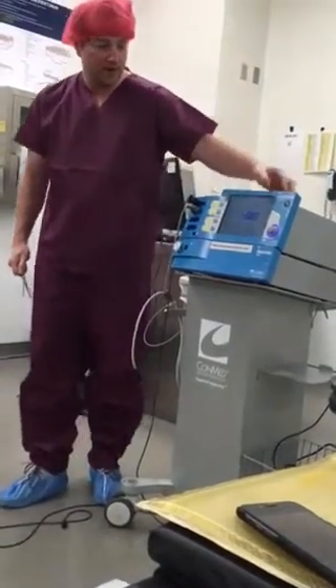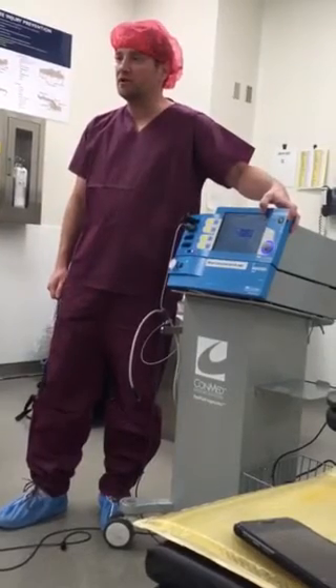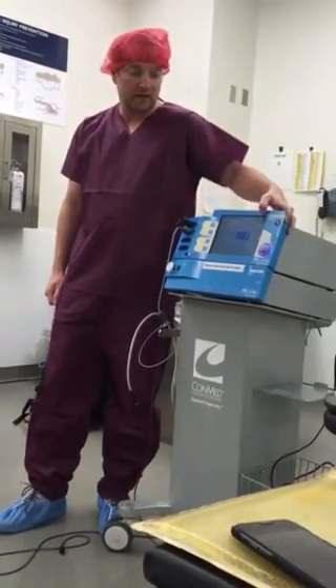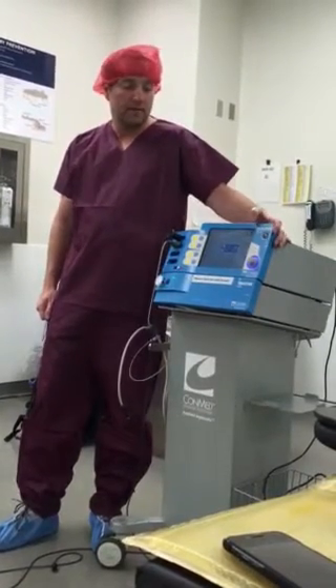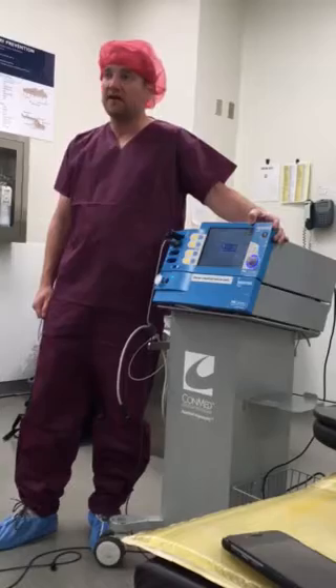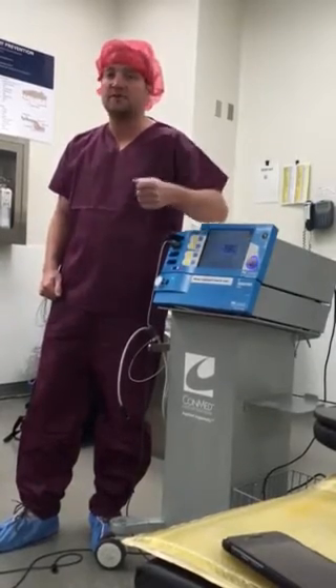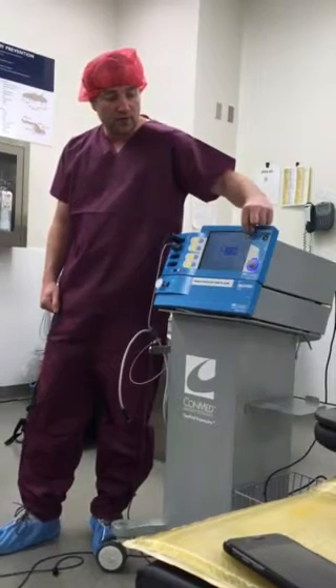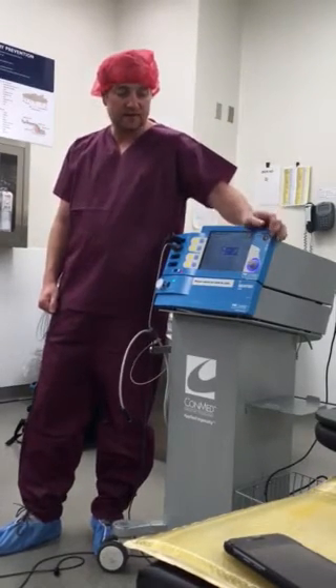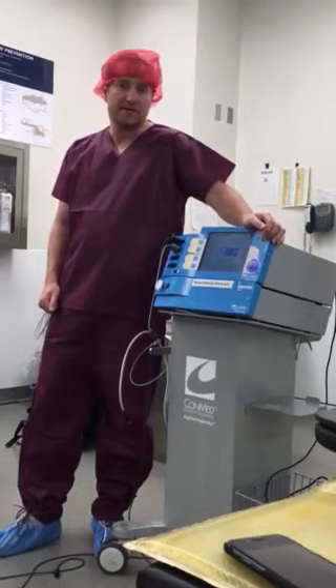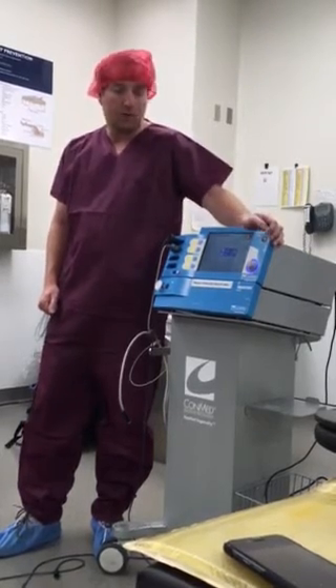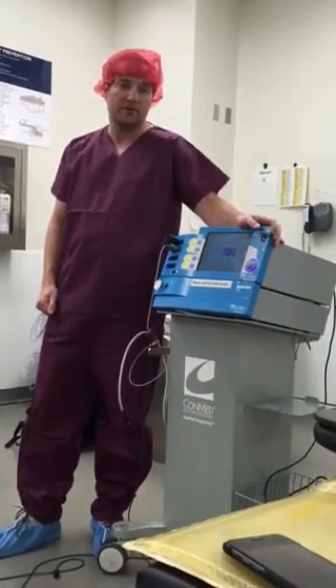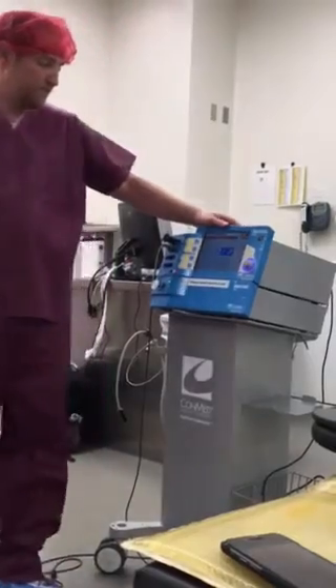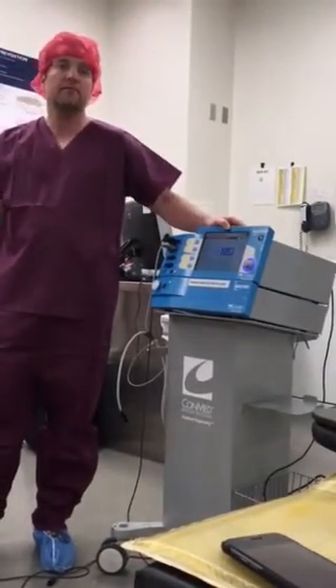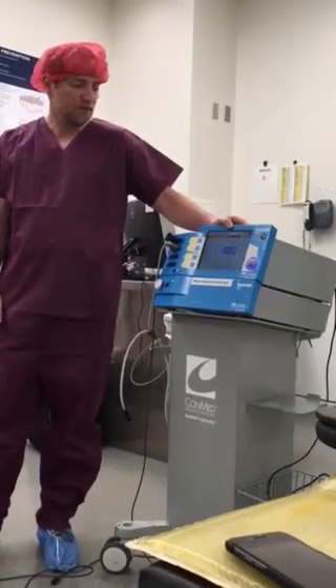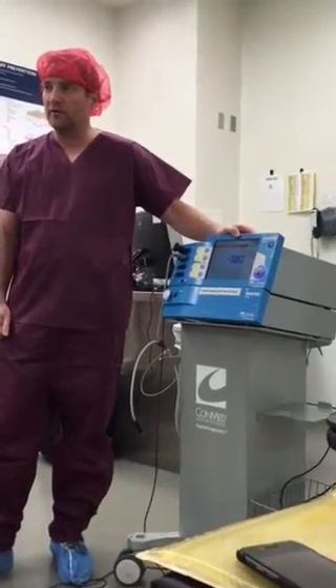You plug it right into here, and this indicator up top is going to tell you how well it's connected to the patient. So that becomes green too. Yes, if you have good contact, this is going to become green. It will not work unless the pad is hooked up. Once the pad is hooked up, if they have it on the table and they get moved around and the pad starts peeling off a bit, you'll see that right here because this shows you how well it's attached to the patient. Once it hits the yellow, it's going to give you a warning light. Once it hits the red, which means it's not connected enough to do the procedure, then it won't activate and you'll get a warning signal that comes up when you're trying to activate it. It'll actually give you this right here: no activation due to neutral electrode error. So it really is pretty foolproof there. It won't activate unless the pad is hooked up properly.